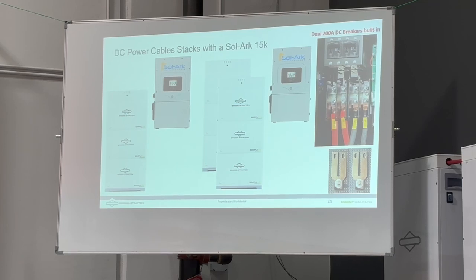The whole reason we have two battery inputs is to meet the NEC code, and the NEC code says that if you put the battery cable in more than 24 inches of conduit, you have to use the standard battery chart in the NEC, and then 4-aught doesn't have the ampacity to run a 15K. In truth, 4-aught cable does have the ampacity to run a 15K, because we're only going to be drawing 250 amps of current, but the NEC doesn't allow you to use the battery cable chart if you're in more than 24 inches of conduit.